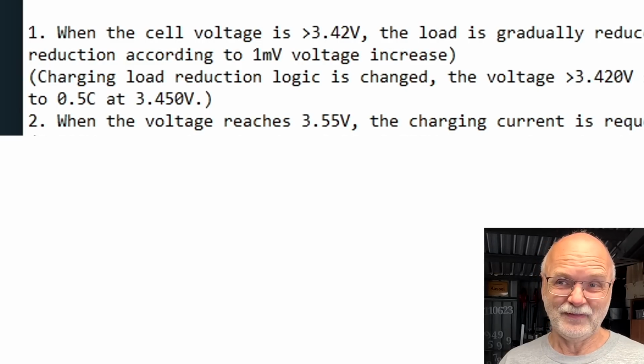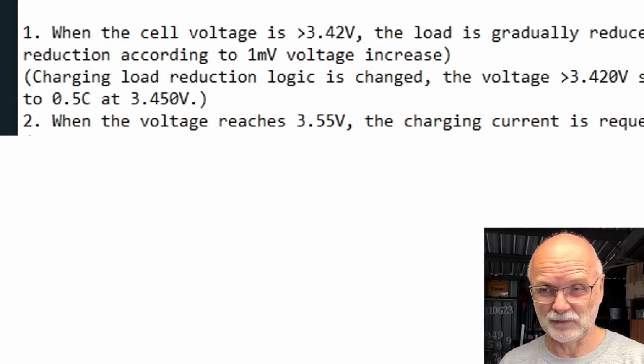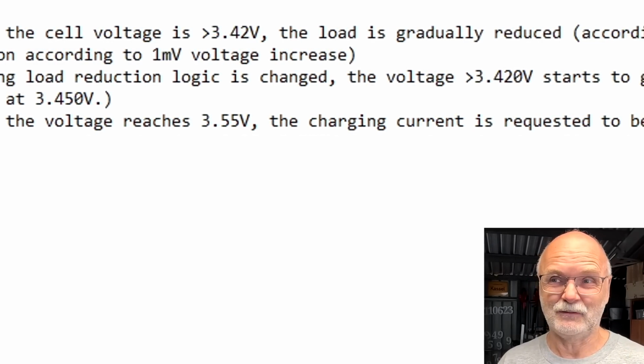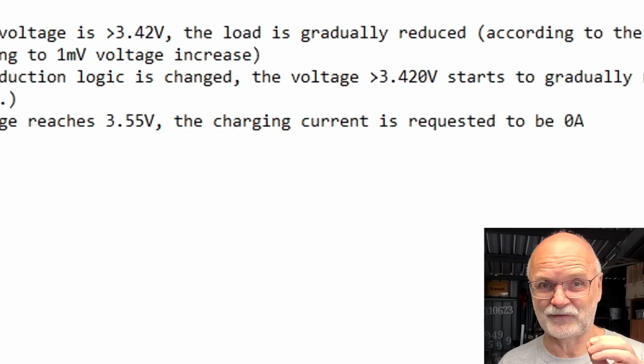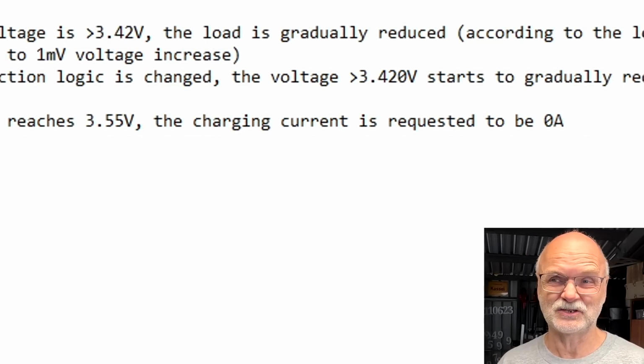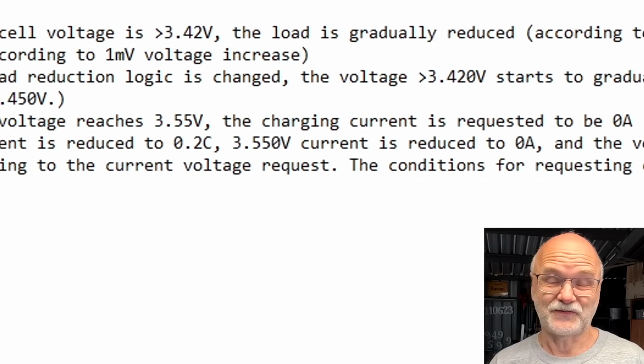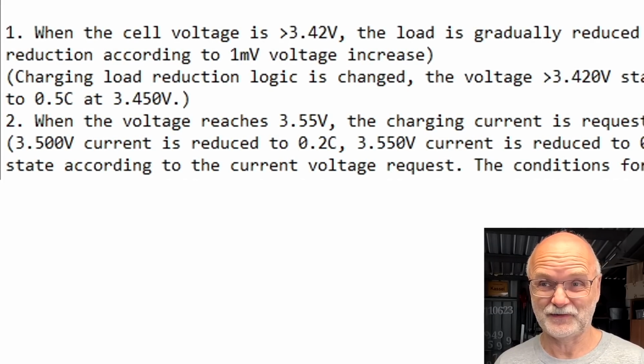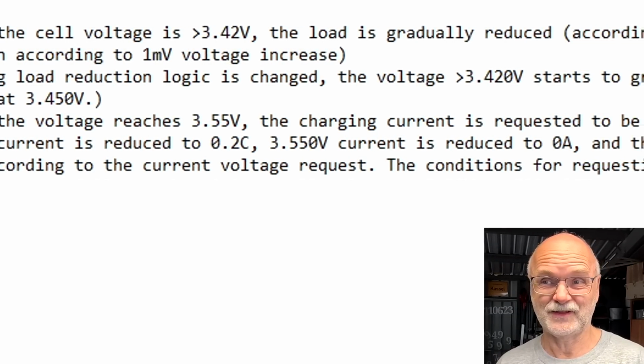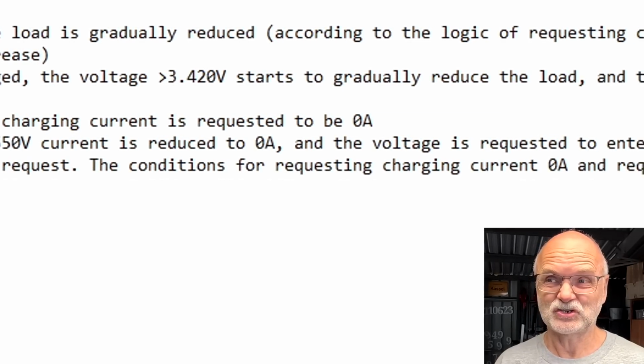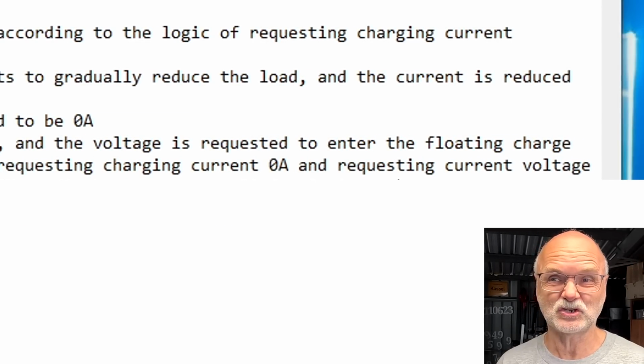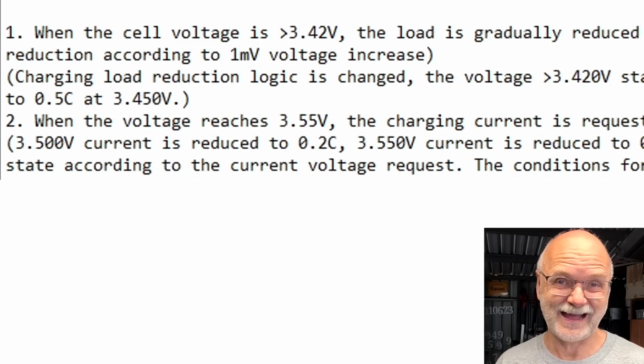Number 2: when the cell voltage reaches 3.55 volts, the charging current is requested to be 0 amps. So we cannot charge the battery any higher than 3.55 volts per cell. It says further: at 3.5 volts, the current is reduced to 0.2C, at 3.55 volts the current is reduced to 0 amps, and the voltage is requested to enter the floating charge state according to the current voltage request. So do we have a float charge state now?